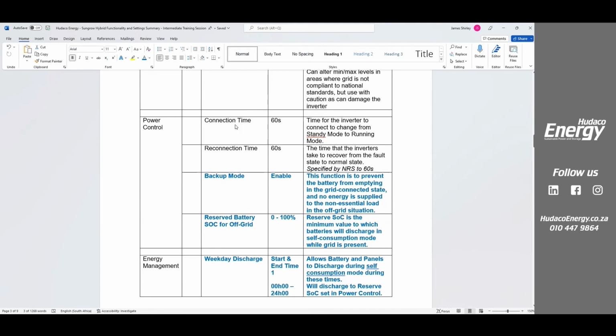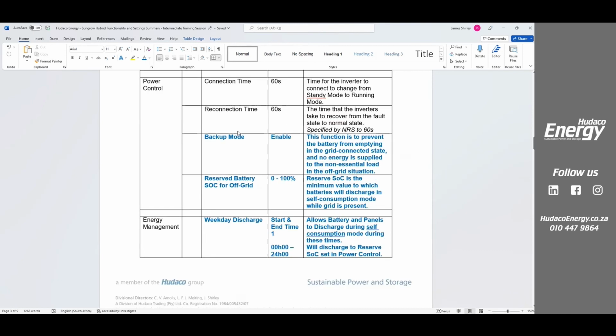The next one is connection time and reconnection time. So this is how long it takes to go from standby to running mode. And this one is how long it takes to return from a fault to running mode. Effectively, NRS tells us we have to have 60 seconds here. Okay, that's a minimum. Here, you can actually set this down to 10 seconds is the shortest time.